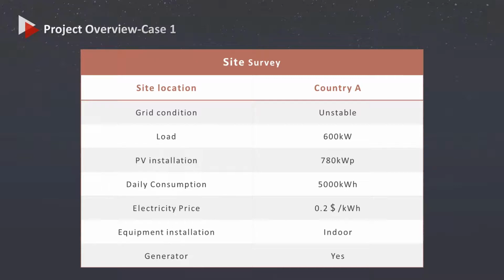Depending on the needs of the project, the design sequence may differ, because some customers may predetermine the PV capacity, while others may predetermine the battery capacity. First, we can choose the inverter model PCS 630 according to the peak load power.